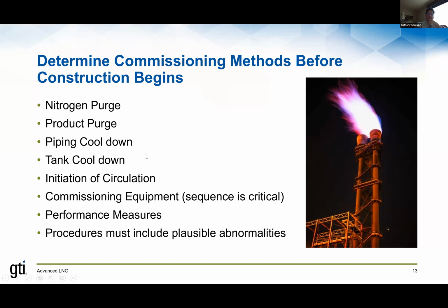How are you going to cool down the piping? We talked briefly about how when you introduce LNG into piping that has not been cooled down yet, that piping shrinks, that piping contracts. The whole piping system moves. So the initial cool down of that piping is very, very critical. You don't want to impart any stresses on that piping that would damage it prior to it actually being used, right? Also, when you have an LNG tank, you have to cool that tank down, and that's a very, very methodical job to cool down a very, very large storage tank. So these are all the considerations that need to be completely thought out ahead of time before commissioning.